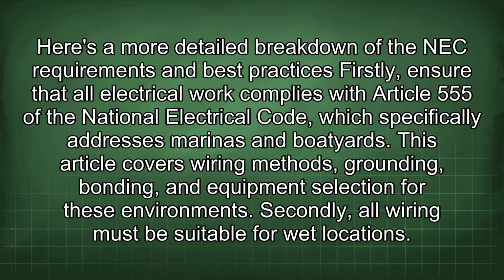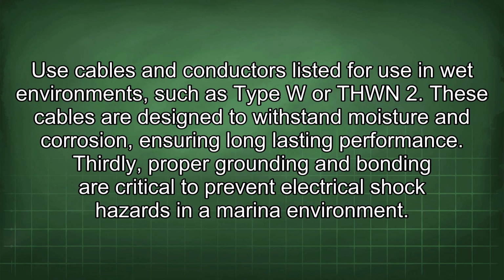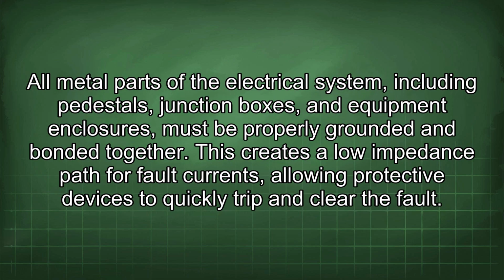Secondly, all wiring must be suitable for wet locations. Use cables and conductors listed for use in wet environments such as Type W or THWN-2. These cables are designed to withstand moisture and corrosion, ensuring long-lasting performance. Thirdly, proper grounding and bonding are critical to prevent electrical shock hazards in a marina environment. All metal parts of the electrical system, including pedestals, junction boxes, and equipment enclosures, must be properly grounded and bonded together. This creates a low impedance path for fault currents, allowing protective devices to quickly trip and clear the fault.